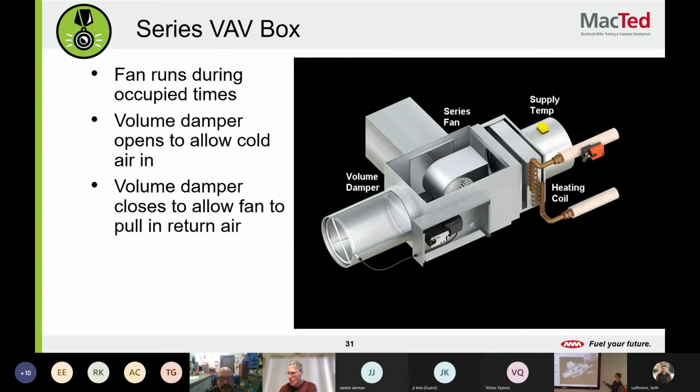And then this is your most common VAV. So again, it's like its own little system. It's going to be that unitary, zone driven. It just cares about one zone, and has the thermostat. On this one, it has a hot water coil on it to raise the temperature of the air if it wants to do that. And then on the return air here, typically there's cold air being supplied to it. So if you want cooling, the water valve shuts, you don't have hot water going through, this damper will open and let cold air through, and then it supplies the space.